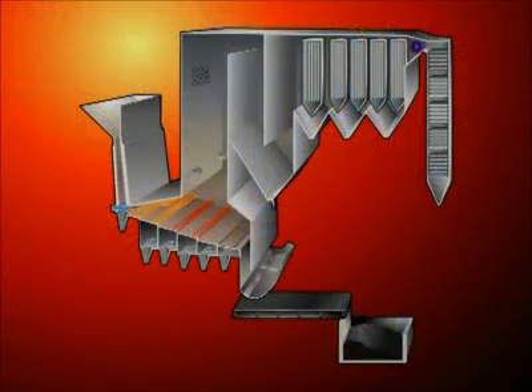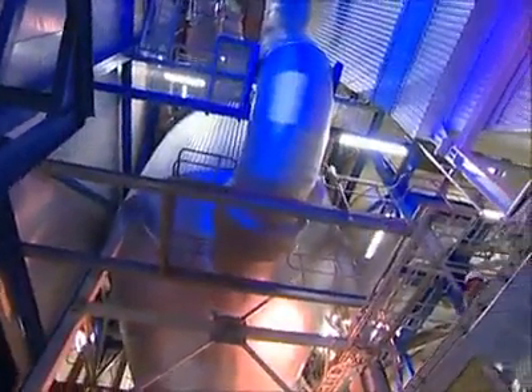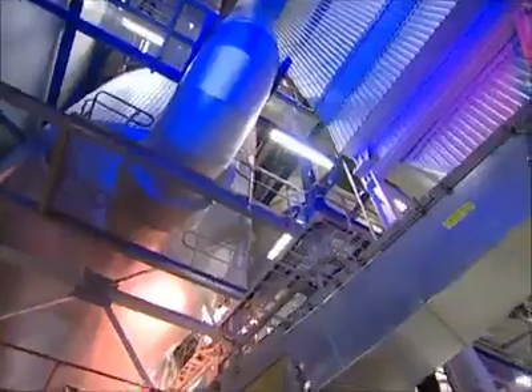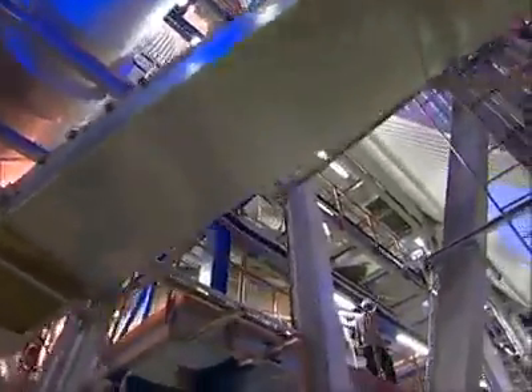After the superheating process, the flue gas is still at around 300 degrees Celsius. Further heat is then extracted by heating the feed water in the economizer pack. The flue gases have by then cooled down to about 160 degrees Celsius and continue to the flue gas purification plant.